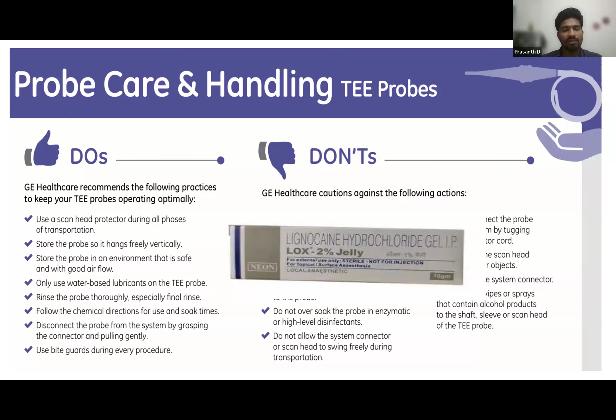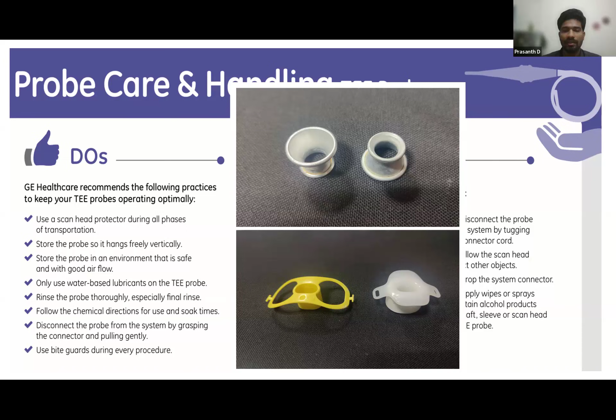What we are using is 2% lignocaine jelly, and rinse the probe thoroughly, especially the final rinse. Whatever the manufacturer of the TEE probe or TEE machine prescribes, we have to use only such chemicals, and even the soak timing is determined by the manufacturer. Disconnect the probe carefully by grasping the connector and pulling gently. And always use bite guards for every procedure. The upper picture shows bite guards for pediatric patients, the yellow one is for pediatric, and the white in the second image is for adult bite guards.